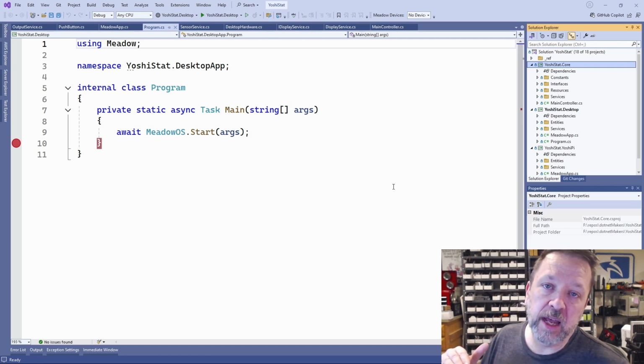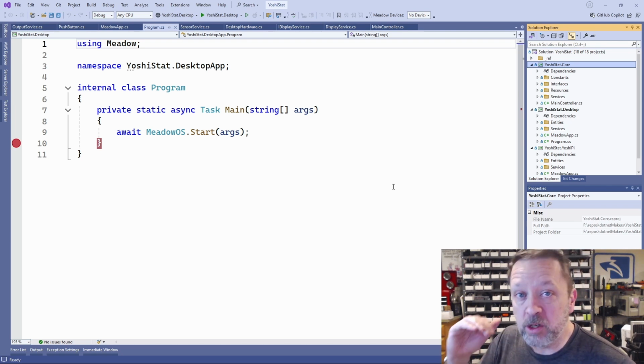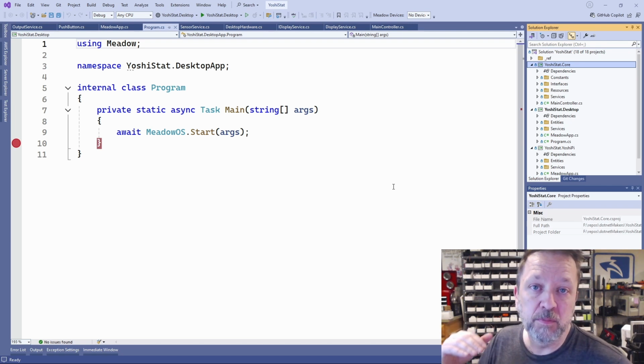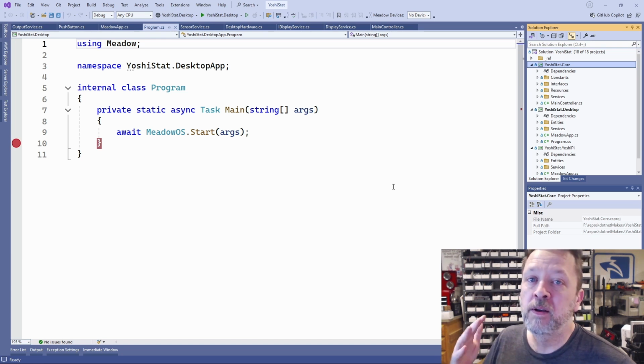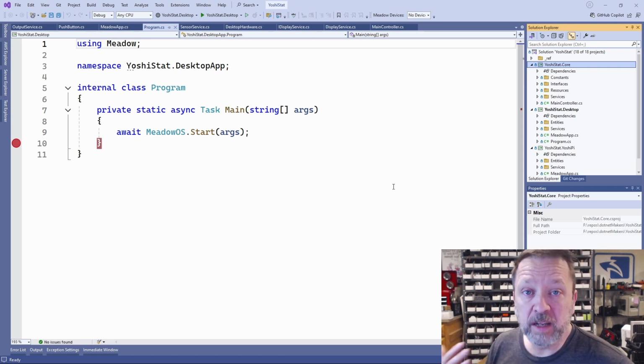You can't just have a target temperature, though, because if you have only a target temperature and you try to drive to it, let's say we're heating, as soon as we go past it, we shut off, and then as soon as it comes back below it, it would turn back on, and you'll get it doing what's called a short cycle. It'll be turning on and off very quickly in succession. You don't want that to happen.